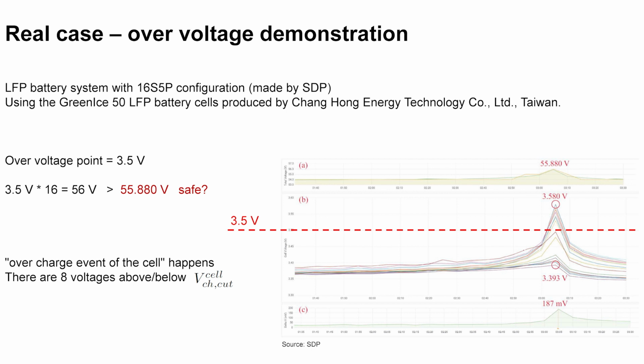The highest voltage is 3.580 V, pointed to by the upper circle in figure B, and the lowest voltage is 3.393 V, pointed to by the lower circle. If V cell high cutoff is set at 3.5 V, there are 8 voltages above V cell high cutoff, indicating that an overcharge event of the cell happens.